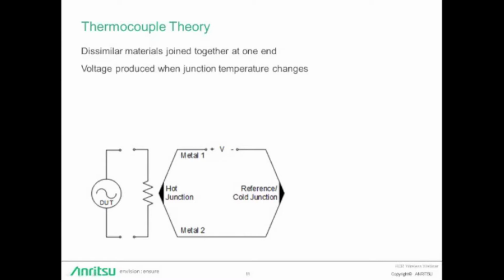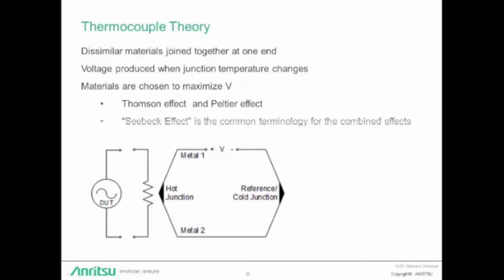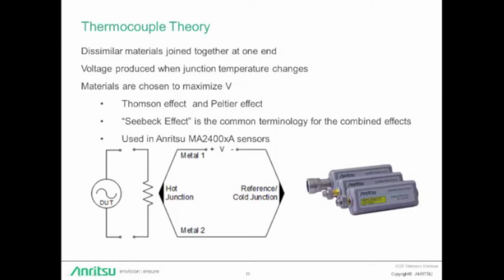The architecture is based on two scientific principles, the Thomson effect and the Peltier effect. Peltier found that junctions of dissimilar metals were heated or cooled depending on the direction in which the electrical current passed through them. Thomson predicted an EMF would arise within a single conductor whenever a temperature gradient was present. So the combination of the Thomson and Peltier effects are referred to as the Seebeck effect, which gives us the fundamental physical model for modern thermocouple detection elements. At Anritsu, thermocouples are used in our MA2400XA sensors.